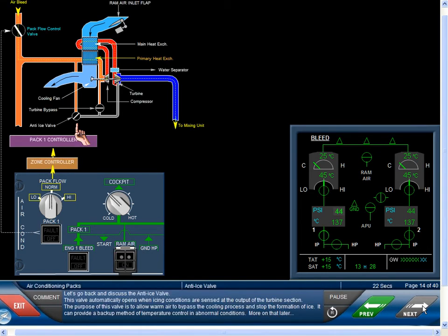Let's go back and discuss the anti-ice valve. This valve automatically opens when icing conditions are sensed at the output of the turbine section. The purpose of this valve is to allow warm air to bypass the cooling process and stop the formation of ice. It can provide a backup method of temperature control in abnormal conditions. More on that later.